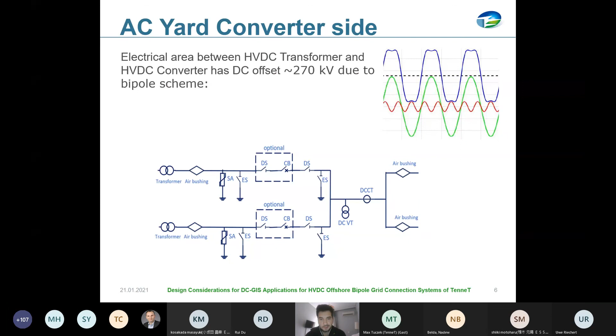The only option in this arrangement will be the presence of a circuit breaker. At the moment, because we rely on air-insulated equipment, there are no circuit breakers, as this would require a lot of additional space reservation. So it is at the moment introduced as an option in our considerations — the breaking capability is not part of the base case, but it is an option because it has certain operational advantages.